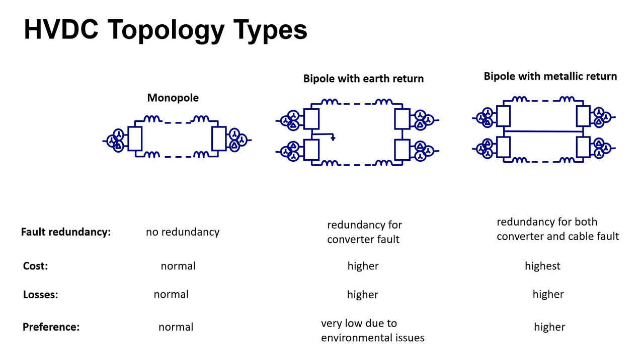Let's look at the redundancy under fault conditions for the monopole topology. What can be seen from the figure is a sending end converter, then a receiving end converter, and the transmission circuit arranged to form a closed loop in order to carry power or current. So if there is a fault in one of the converters, either the sending end converter or the receiving end converter, or in one of the transmission lines or circuit, then the loop will be broken. And there will be no path for the current to circulate anymore between the two ends, meaning all power is lost, and there is no redundancy with this topology against fault.